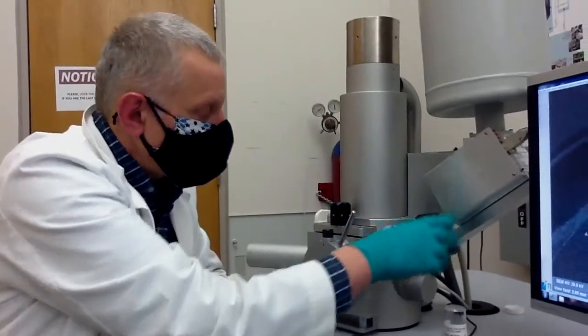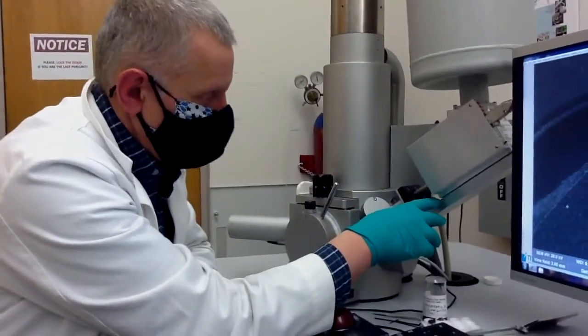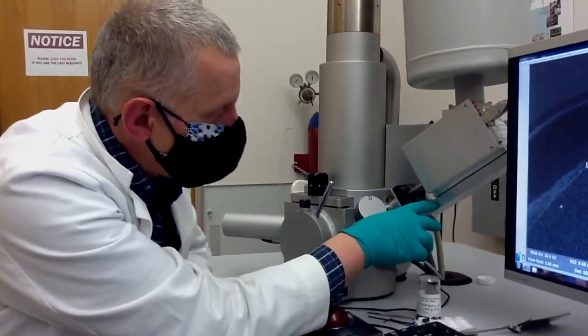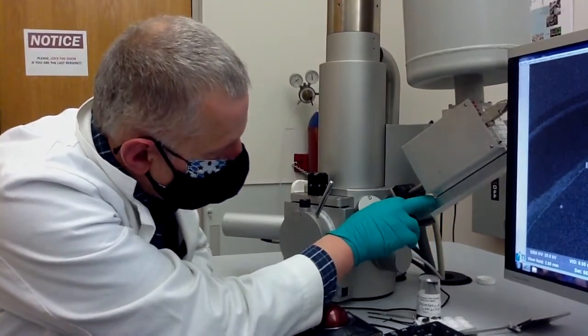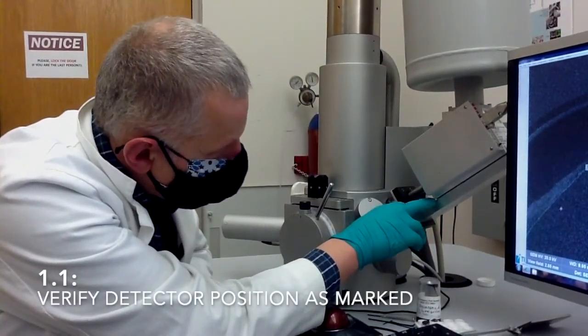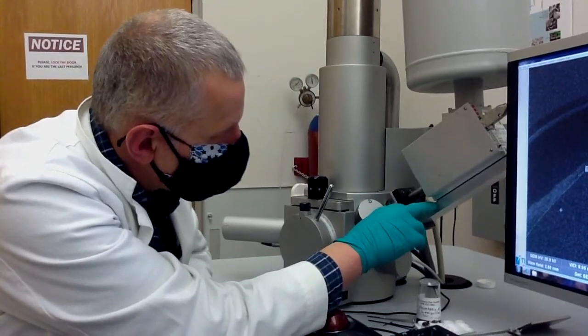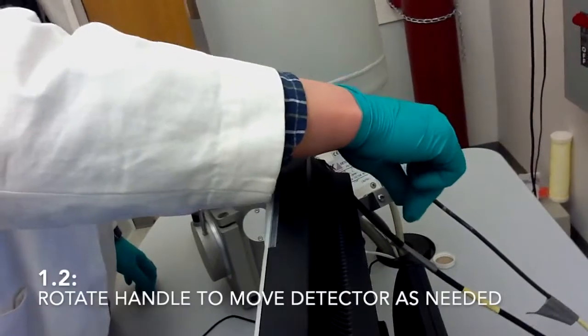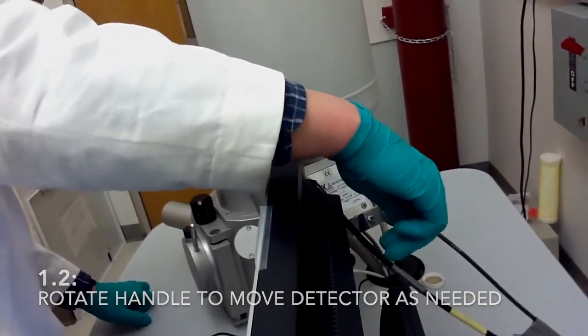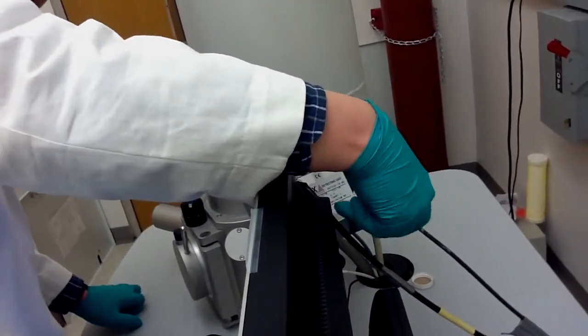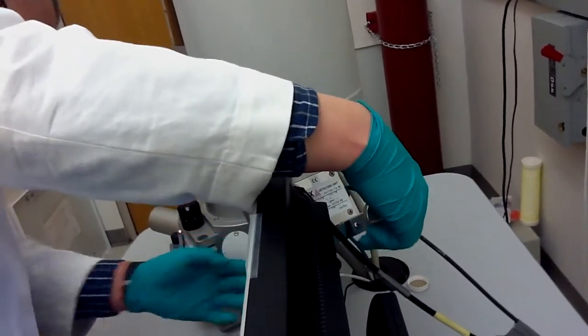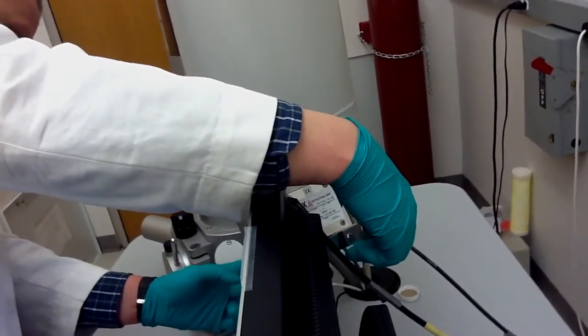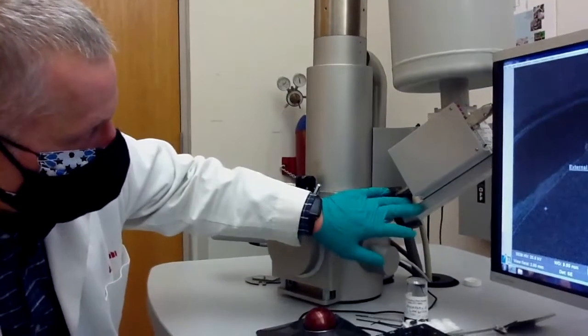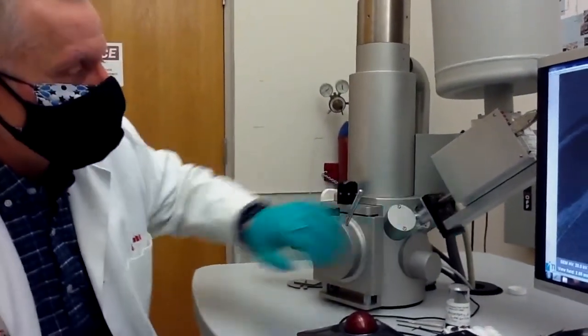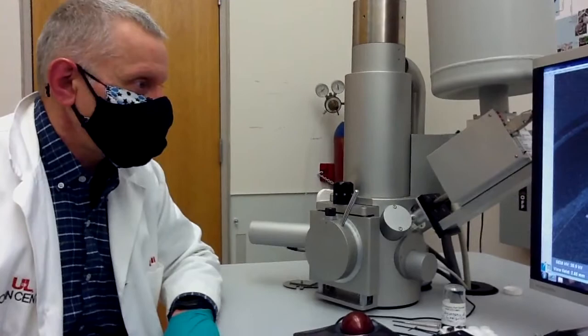Now, the detector also needs to be at the right distance from your sample. So if everything is well aligned, we have a mark here, a red mark. The detector should be at this position. If it's not, there is a handle here. You can just rotate this handle to move the detector closer to the sample or farther. But basically, you just need to bring it to this point where there is this red mark. Make sure that it's around this position. This gives you the optimum signal.